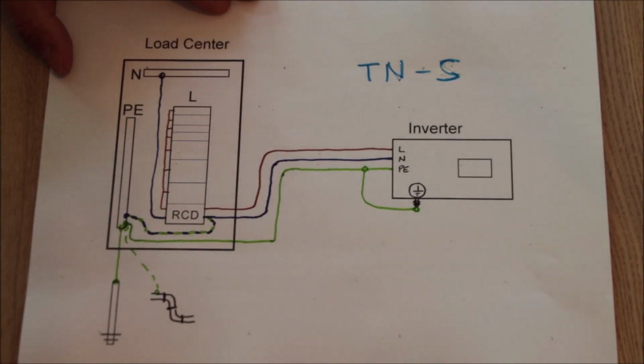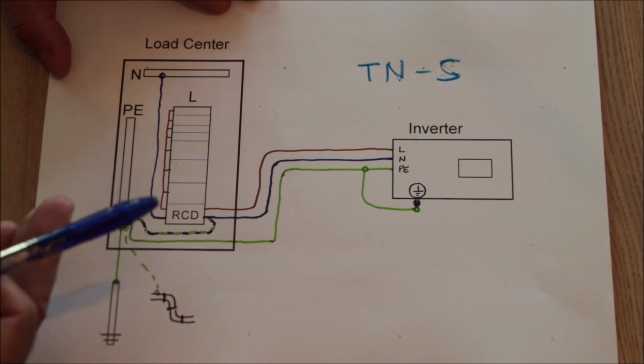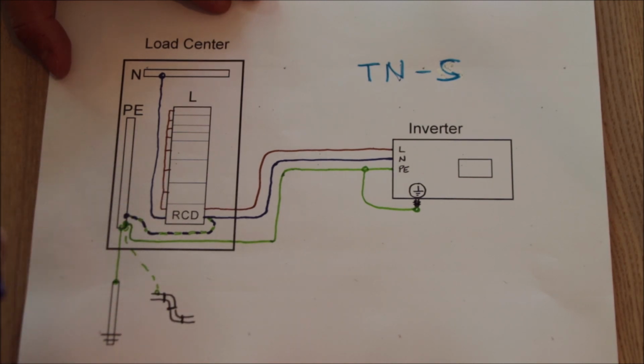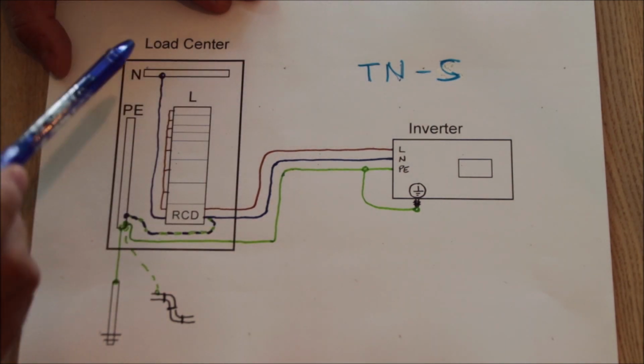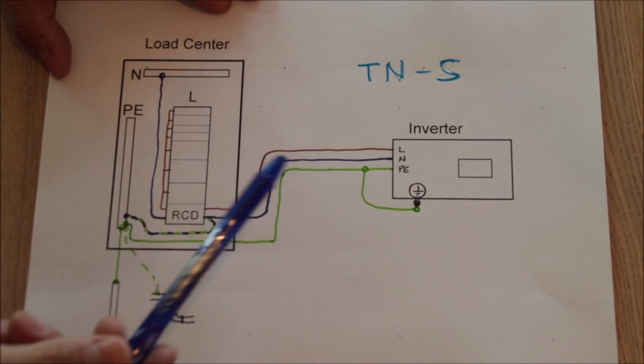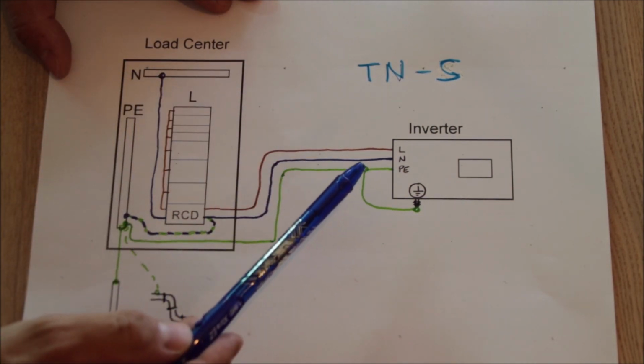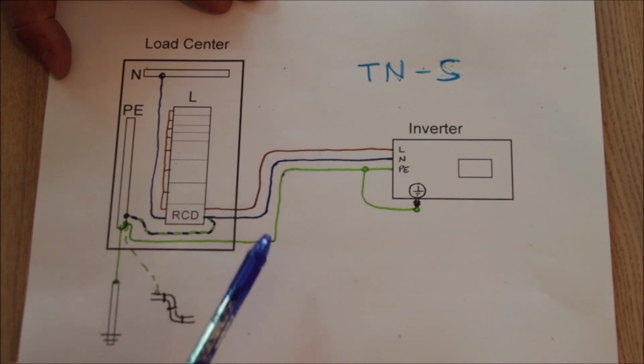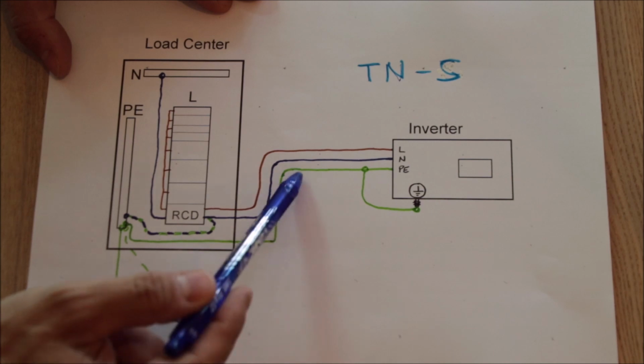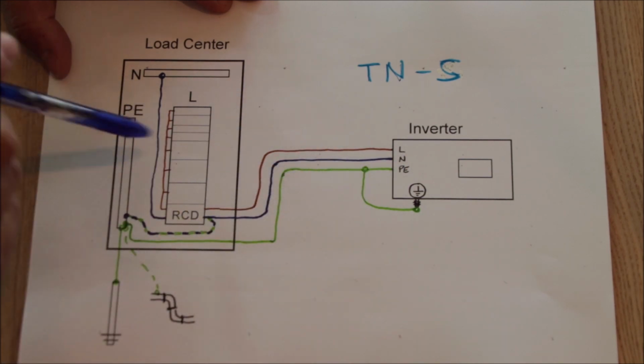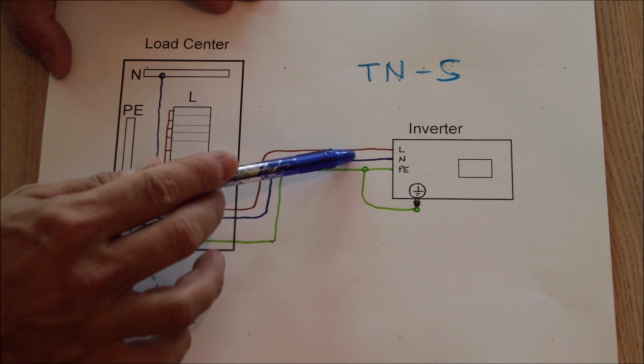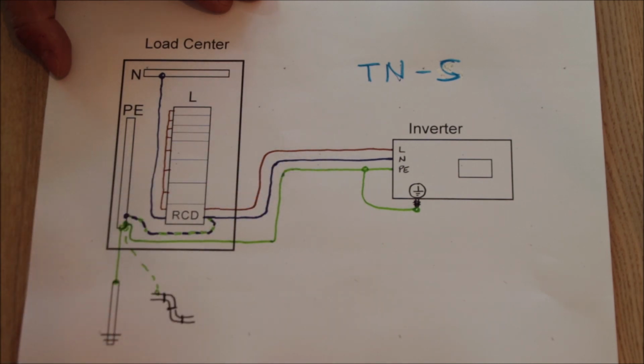So every time we build up a small system at home, we will go for the TN-S system, because that system gives us already a return path, a double return path. So in case of an earthing fault, a return path to the source of power with 2 wires, more or less, right? Because N and PE are anyway connected, somewhere bonded.